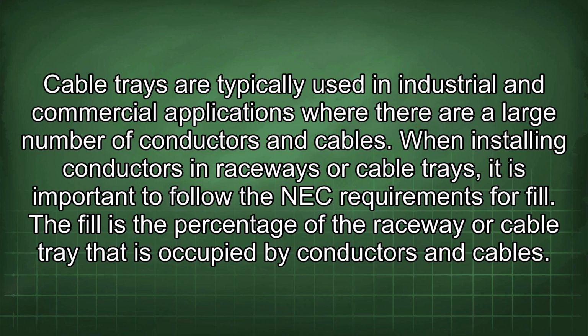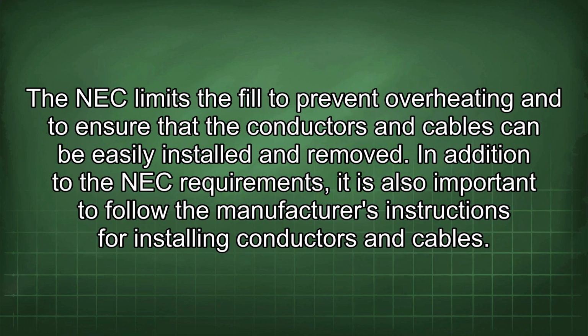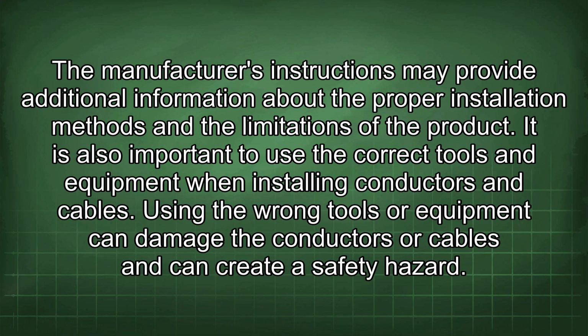When installing conductors in raceways or cable trays, it is important to follow the NEC requirements for fill. The fill is the percentage of the raceway or cable tray that is occupied by conductors and cables. The NEC limits the fill to prevent overheating and to ensure that the conductors and cables can be easily installed and removed. In addition to the NEC requirements, it is also important to follow the manufacturer's instructions for installing conductors and cables. The manufacturer's instructions may provide additional information about the proper installation methods and the limitations of the product.